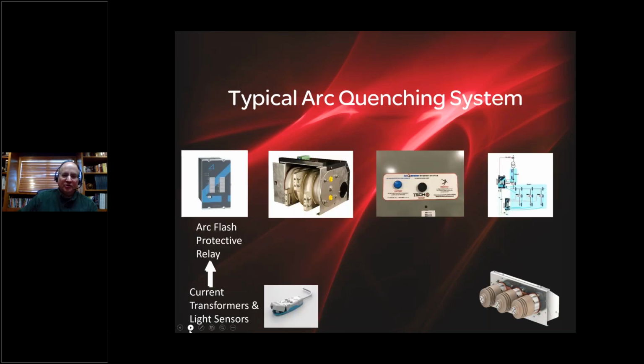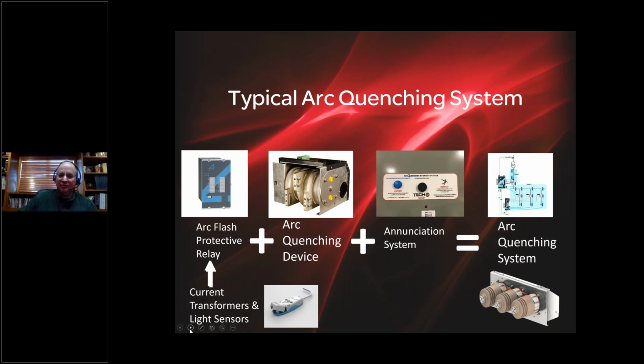So a typical arc quenching system that we have here, we're going to take our CTs and light sensors, connect them to a protective relay, and attach that to an arc quenching device. The connection between those two, by the way, is via a fiber optic cable. We include an annunciation system that's typically attached as well. There's a controller that's part of this that attaches to a plant SCADA system, and that creates the complete arc quenching system.